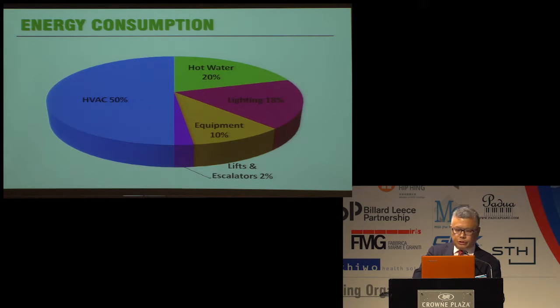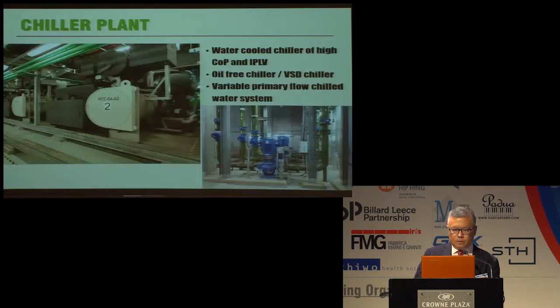There are several ways to reduce the energy consumption of HVAC systems. First of all, a well-designed building envelope can minimize the solar and thermal heat gain, and therefore reduce the need for air conditioning at source. Then we can look into the HVAC equipment efficiency. The central chiller plant should be selected based on not only the COP, which is the efficiency under full load condition, but also part load performance, as these plants rarely operate at full load. So a high integrated part load value, the IPLV, should be specified. Also, oil-free chillers and variable speed chillers have very good part load efficiencies, and they are becoming more affordable nowadays.